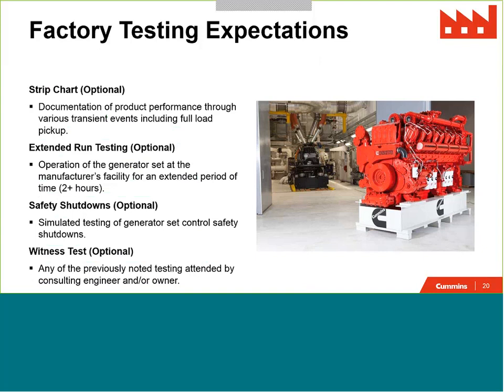There are lots of options for optional testing. Many generator set manufacturers, I'd say all or most, are willing to go above and beyond to meet your specific factory and site testing requirements. It's just important to note that if you have those specific requirements that you want to see met, that you specify those clearly. So things like including additional documentation such as a strip chart to demonstrate and to record the performance of the product as it goes through its site testing. Extended run testing is also quite common, especially for larger projects, and this is where you may run a product for 2 or more hours in a manufacturer's facility.